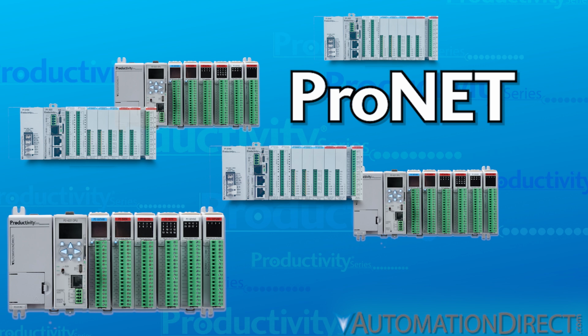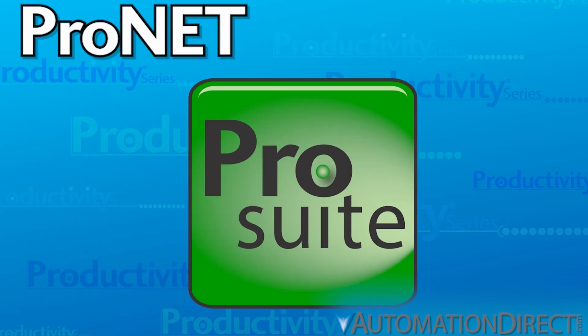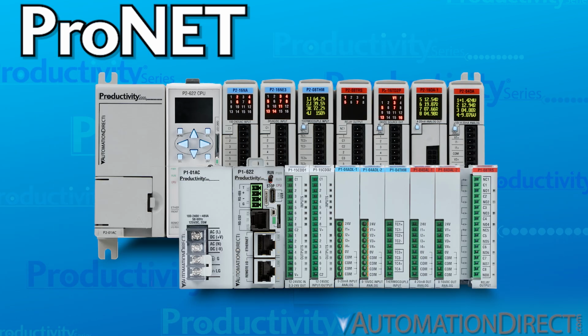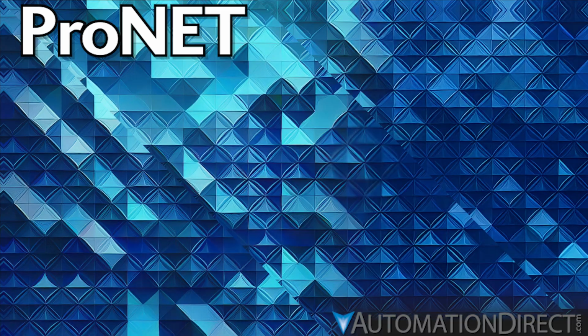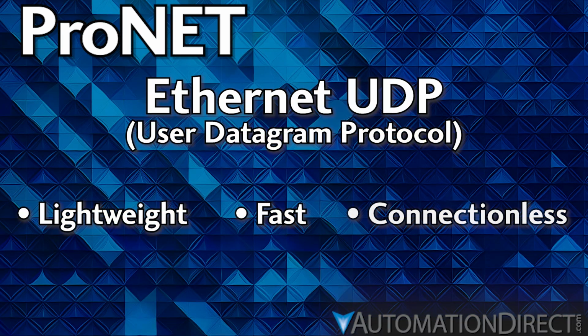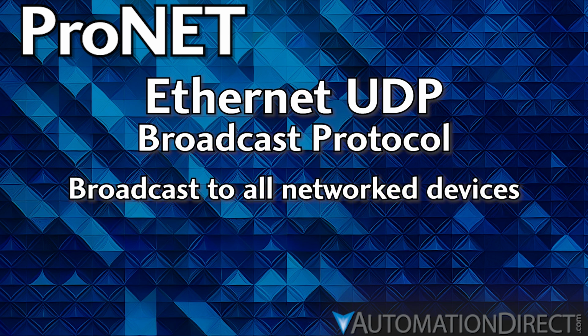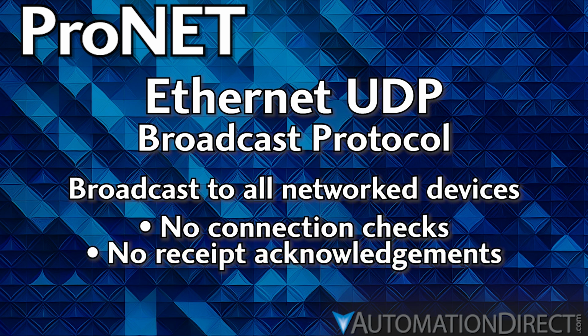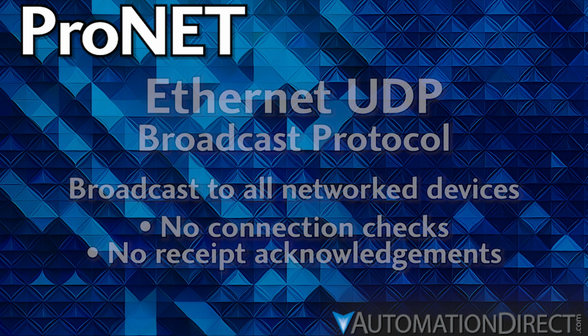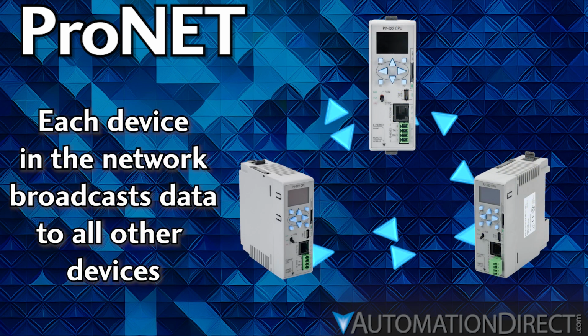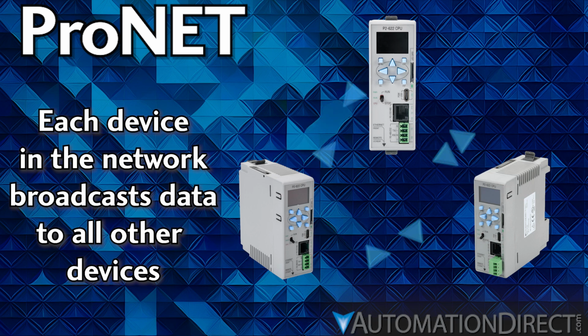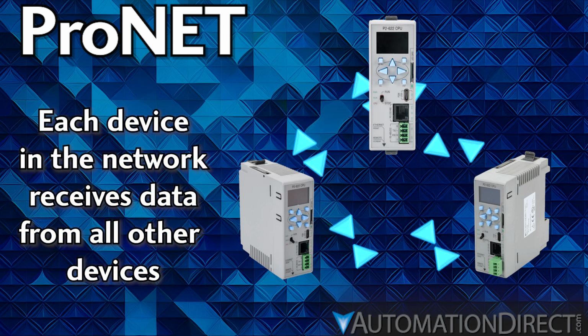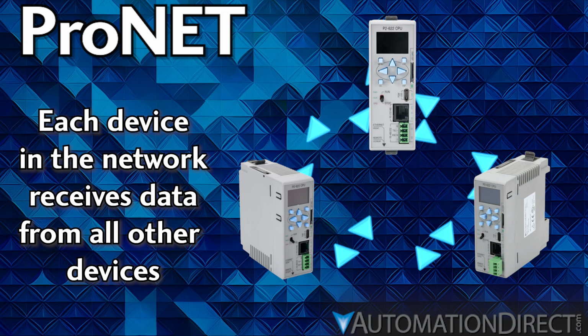ProNET. Built into the Productivity Suite software, it allows Productivity line PLCs to easily share data via Ethernet UDP. As you recall, UDP is a lightweight and fast connectionless broadcast protocol. Data is broadcast to all network nodes without point-to-point connection checks or receipt acknowledgments. Each configured Productivity broadcasts its selected data to all others in a ProNET network and conversely receives the data broadcast by each of the others.